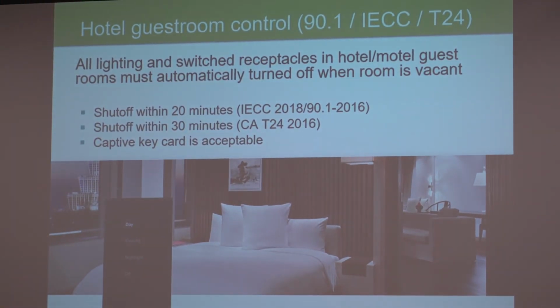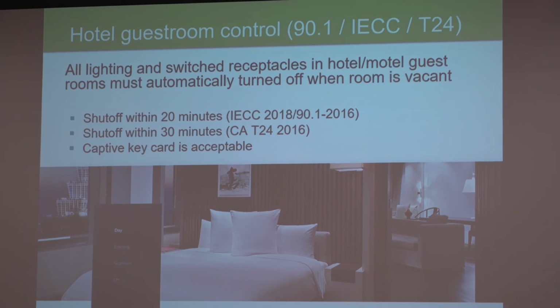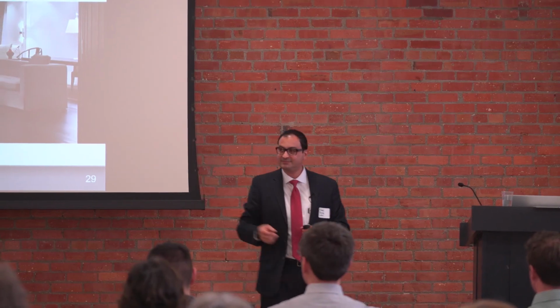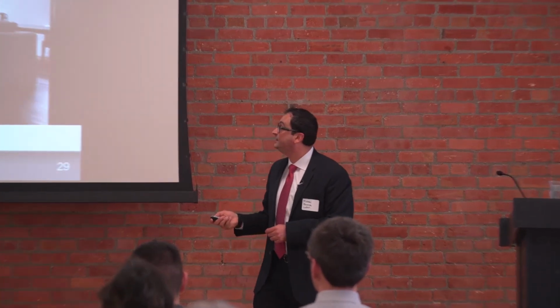Hotel guest rooms. So this has changed a lot in the latest energy code. So now, in the latest codes, when a guest room is vacant by more than 20 minutes, all the lighting has to be automatically shut off, okay? And that includes the plugged-in lights, okay? So it used to be all you needed was a manual light control at the entrance of the guest room to control only the permanent hardwired lighting in the room, okay? Which, for the standard guest rooms, is usually just the one light under the door. But now they added all the lights, okay?